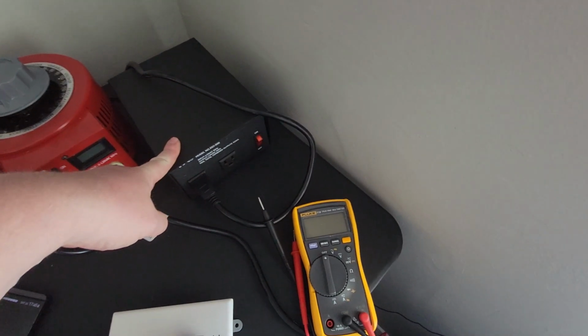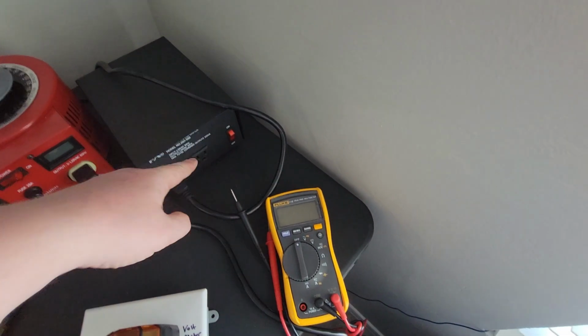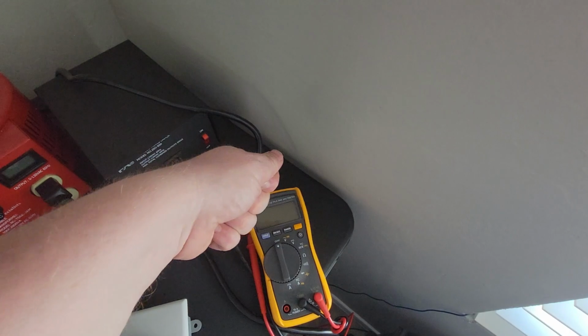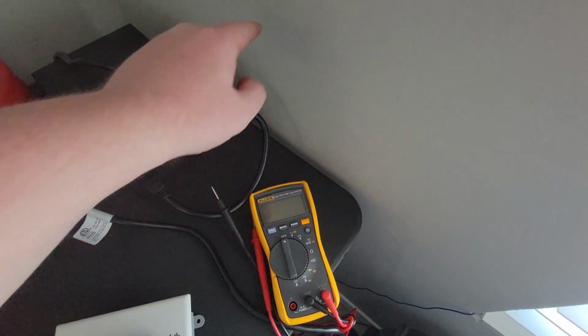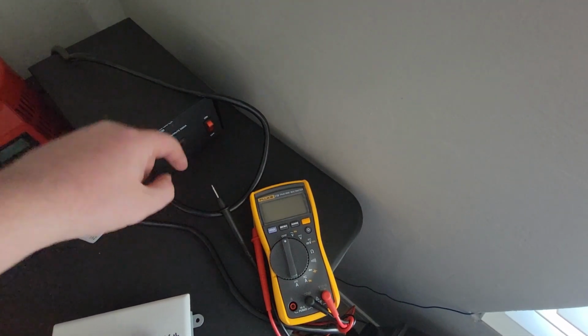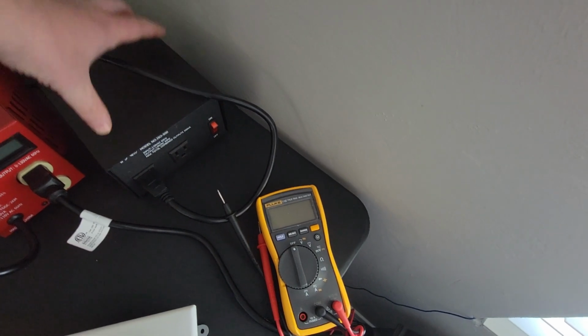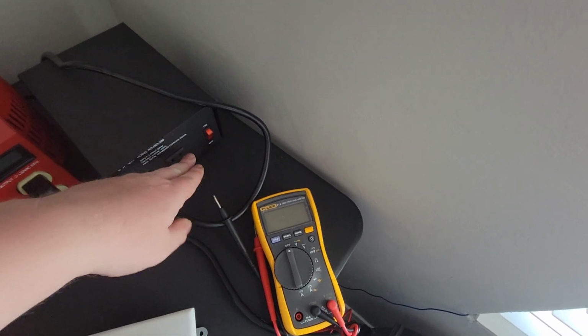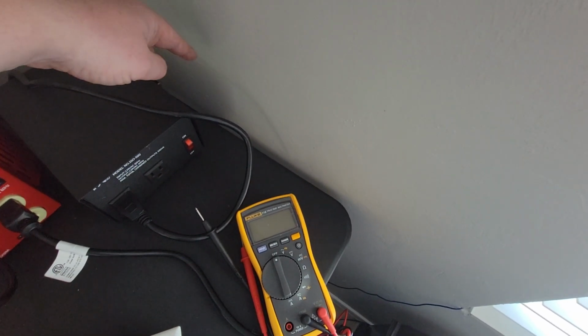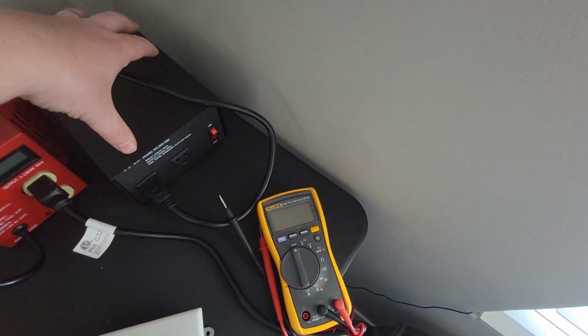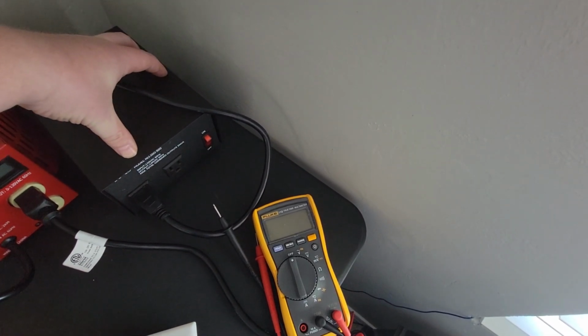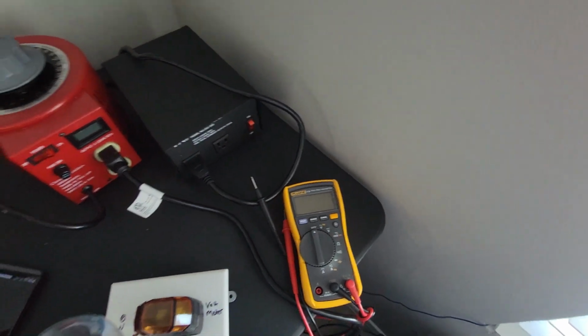Now, how do I know that this transformer is isolated? Well, I test from the plug in the wall between neutral on that to neutral at this socket, and nothing is connected—there is no continuity. Same thing with the hot: hot on the plug, hot in here. I think I already had a video demonstrating that. No continuity, so this is fully isolated.